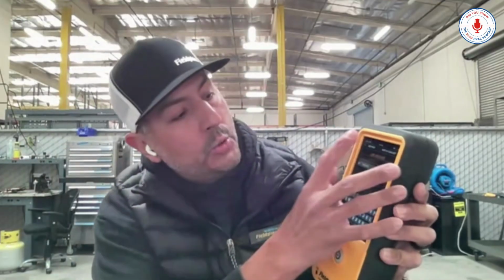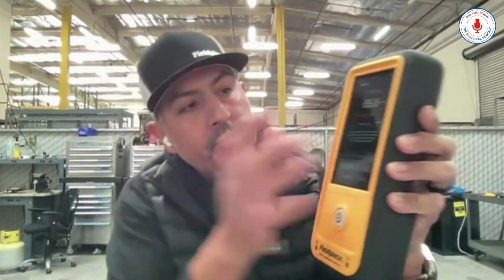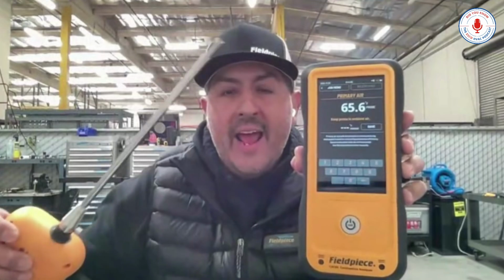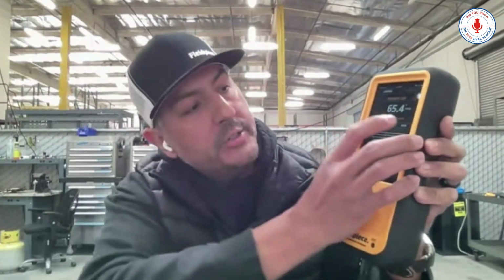Sure. And so with this tool, you can just go to this button that says primary air, and now you're in the primary air screen and you are standing by the appliance. You can save that in there. And now you've updated the primary air that's saved to support a more accurate combustion analysis calculation. Okay. Not a lot of people think about that, but it's something to help ensure that you get the most accurate measurements and calculations.